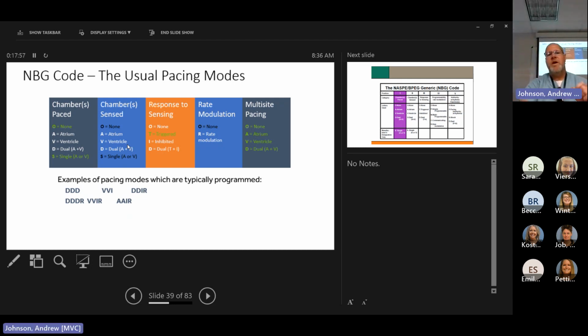The next one is the response to it. Are we going to inhibit or are we going to trigger? What does that mean? Technically, we do not use trigger very often, so really the inhibit is what we do use. The trigger would mean if I see a ventricular complex, boom, I'm going to come in 20 milliseconds after I see that and provide a beat. Why would we do that? Usually it's because we're trying to get that left side to come across as quickly as possible.